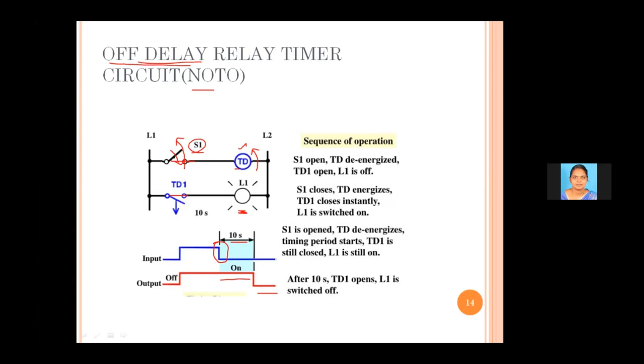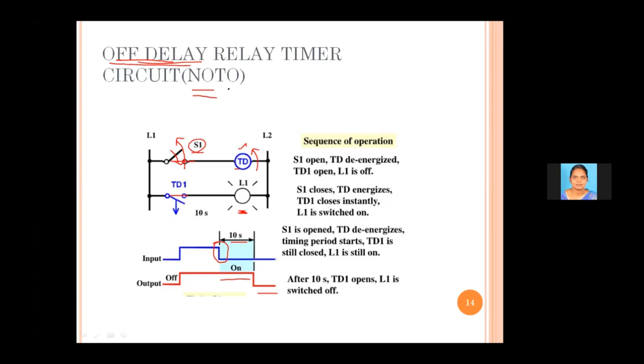But after I put my switch to the open condition, my timer now goes to the off state. So I'm giving an off delay, a delay of 10 seconds. Once I put my switch in the off state, it takes a delay of 10 seconds to make my output go to the low level. That is my lamp going to the switch off condition. This is the timing diagram, or the type of output, which you'll get when we use an off delay timer along with the normally open type timers.